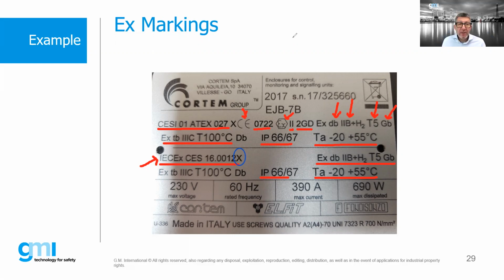Yeah. For example, in GMI, glad you brought that up. Typically, the GMI barrier would have an X certificate, an X at the end of the certification, because they're designed for installation in zone 2, but they cannot be placed in zone 2 as is because they're IP20, and IP54 is a minimum requirement. So the X would say, please install in a suitable enclosure. So yes, very important to look at the X, because it might limit your installation. And as you said, Bob, very clearly, when you go out to have an inspection, you're going to run into big trouble.